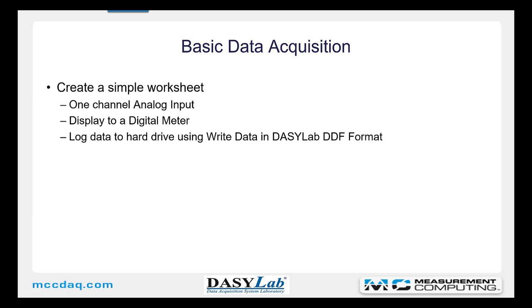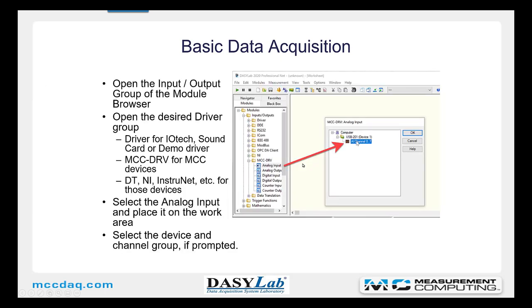We're going to create a simple worksheet with a one-channel analog input displayed to a digital meter, and then log data to the hard drive using the write data module in DASYLab DDF format. The first step is to open the input-output group of the module browser, then open the desired driver group. You can use the IOTech sound card or demo driver, the measurement computing MCCDRV driver, or any other driver that you have configured. Select the analog input and place it onto the work area. Select the device and channel group if prompted. I'll show you a quick animation of how that works.